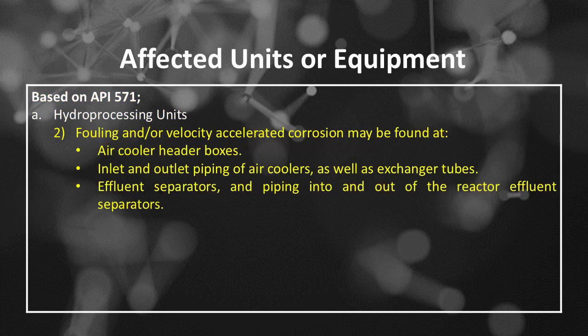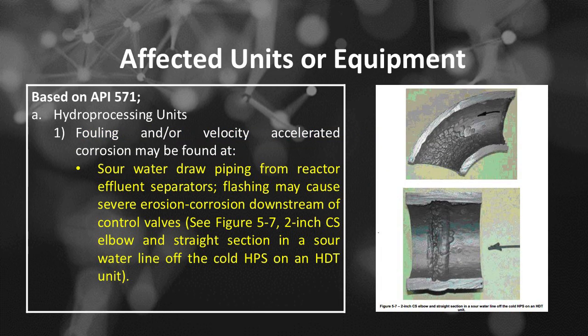Number 2. Fouling and/or velocity-accelerated corrosion may be found at air cooler header boxes, inlet and outlet piping of air coolers, as well as exchanger tubes, effluent separators, and piping into and out of the reactor effluent separators. Sour water draw piping from reactor effluent separators. Flashing may cause severe erosion corrosion downstream of control valves.